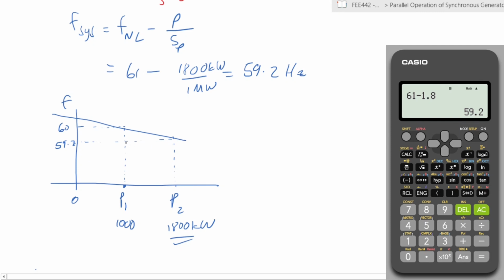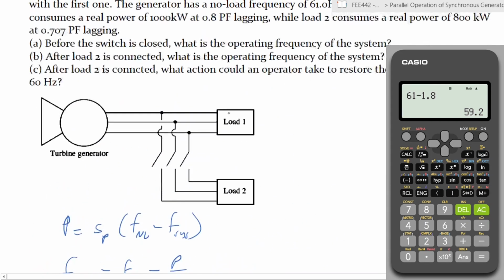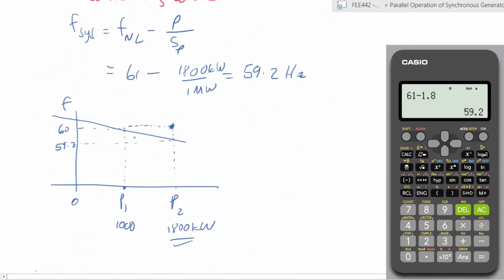So you need to change your set point such that the P itself is at this point, right? Because you want to operate at 60 hertz. You want to bring it back to 60 hertz that we had in the previous example. So what we then do is what we talked about, the set points. You will change the governor set points from this to this. So this is set point number 2, right? This is done by changing the governor.